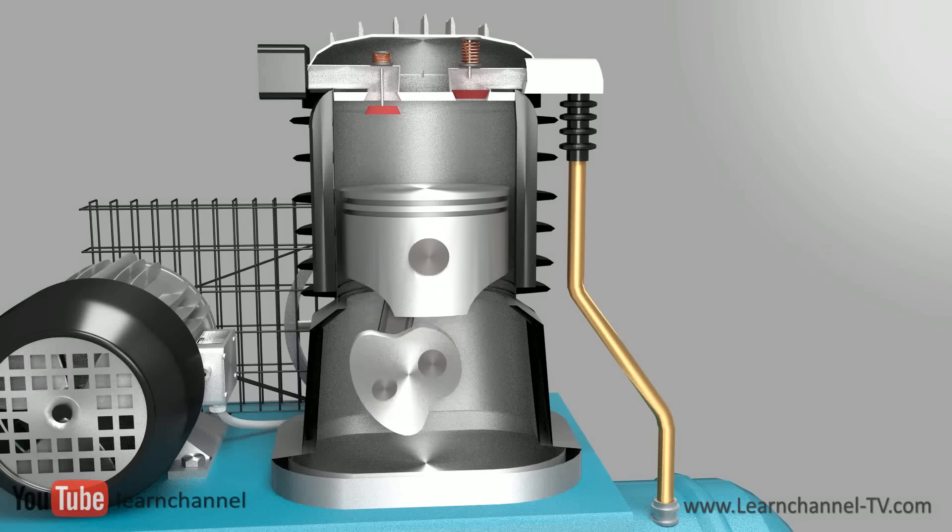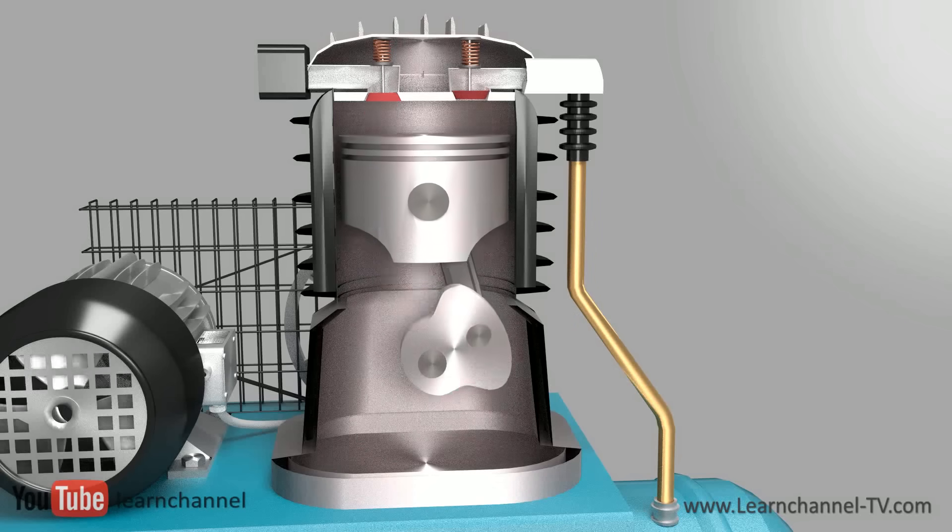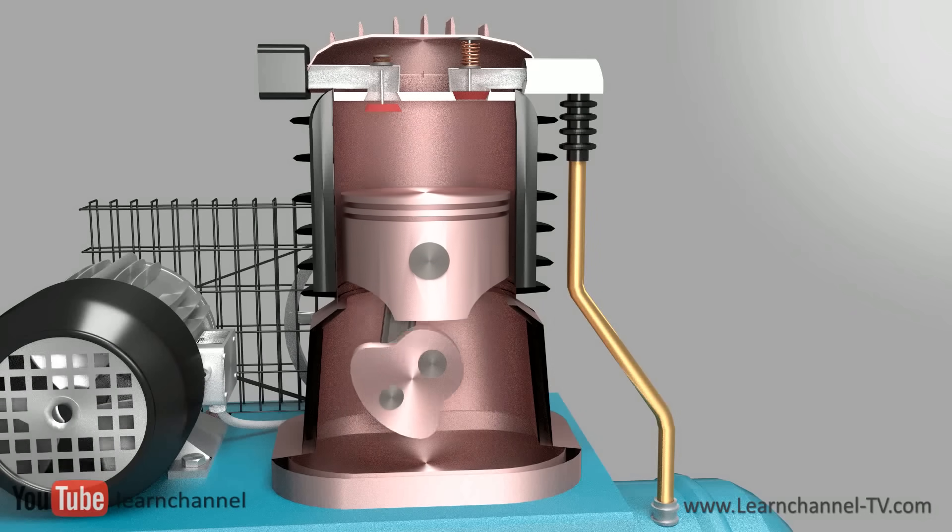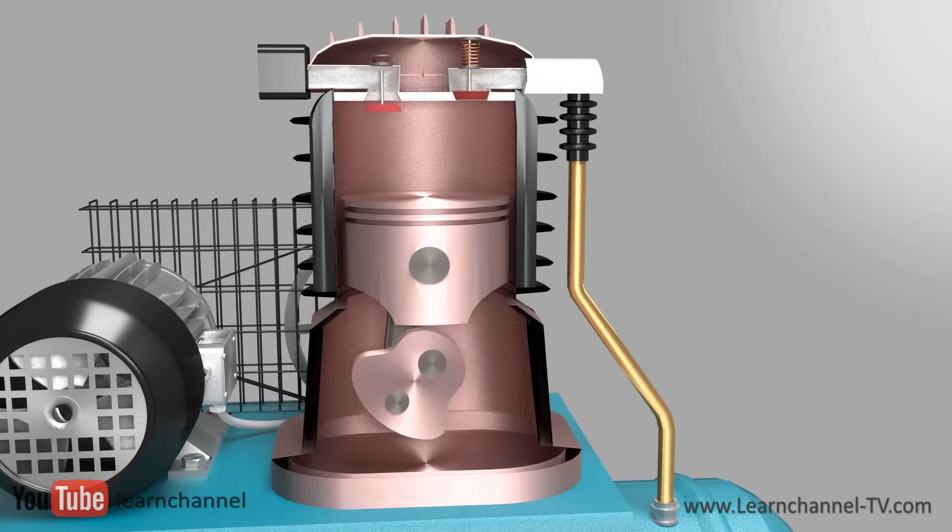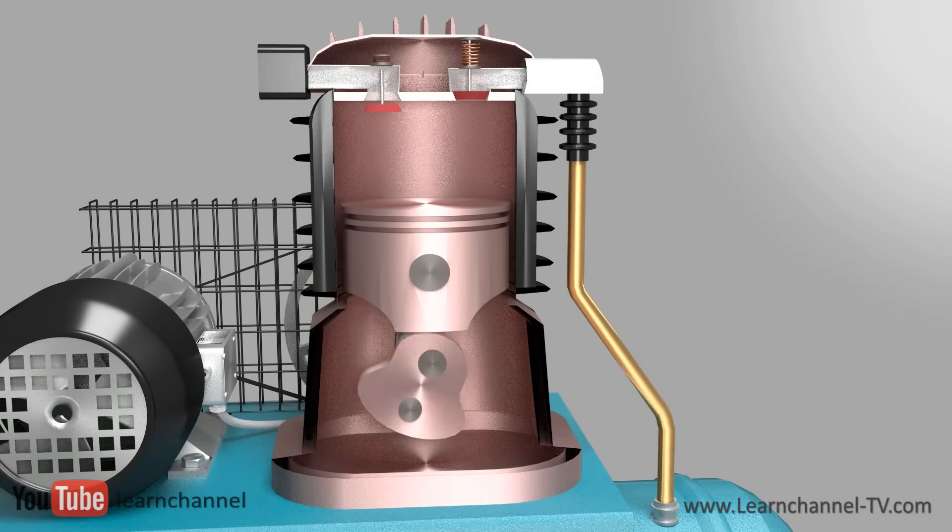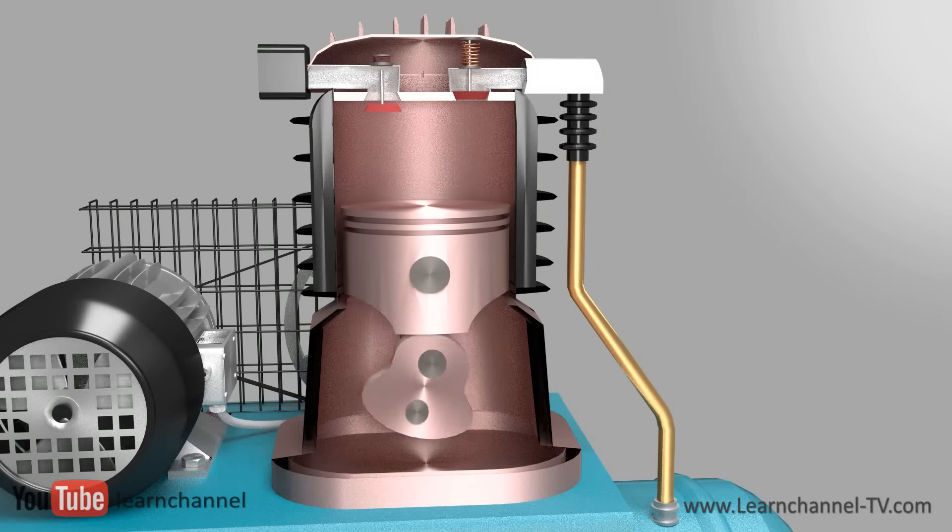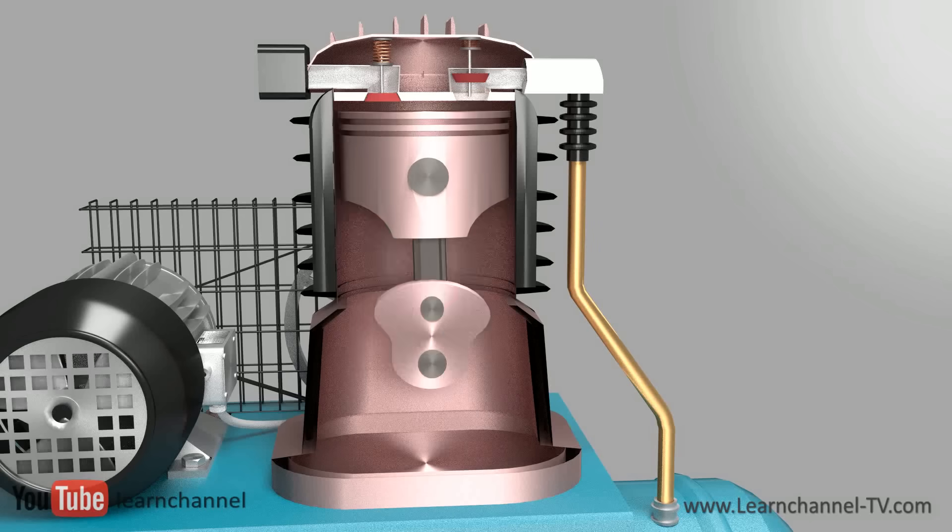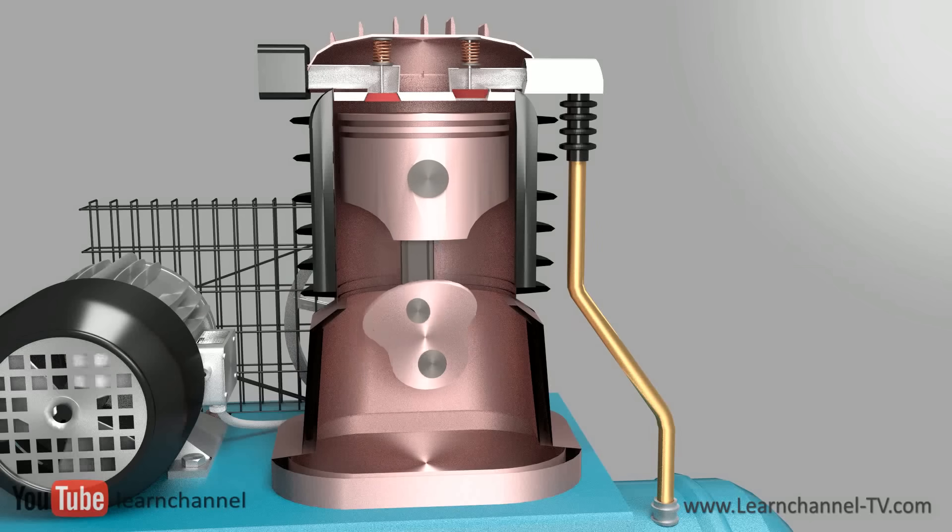Air heats up when it is compressed. This is a problem of each compressor. The result is not only a less efficient compression cycle, but also a real danger of explosion if any inflammable substances, such as oil or lubricant, get contact with the overheated air and piston. Therefore, the compression of a single-stage compressor is limited to an output pressure of about 10 bars, or 145 psi.